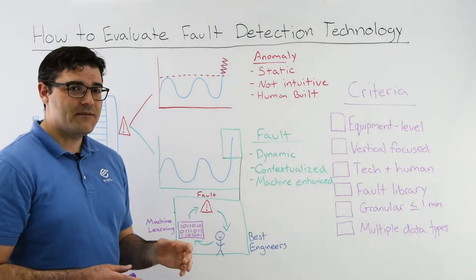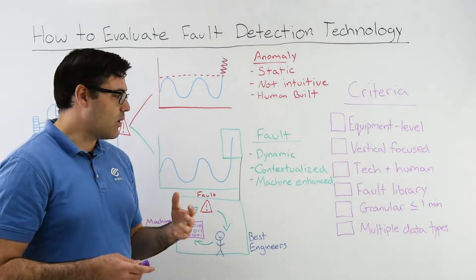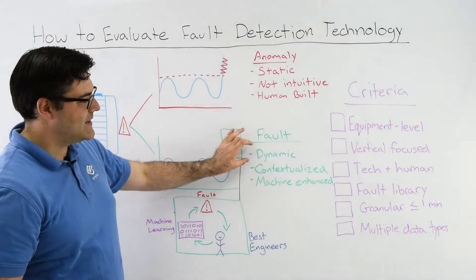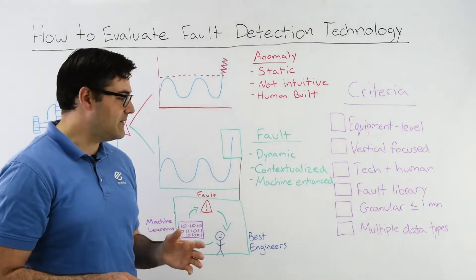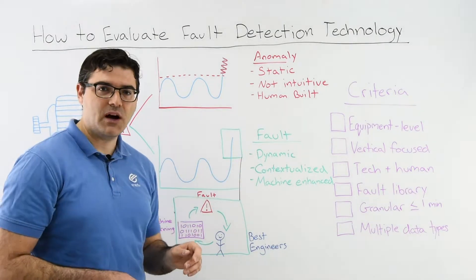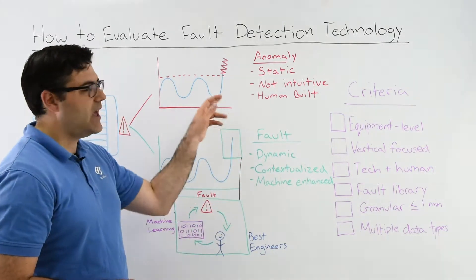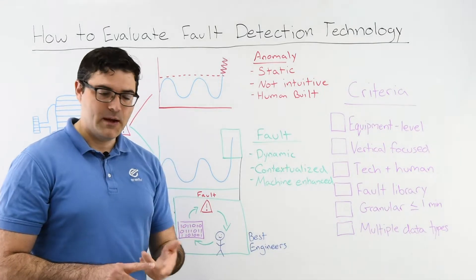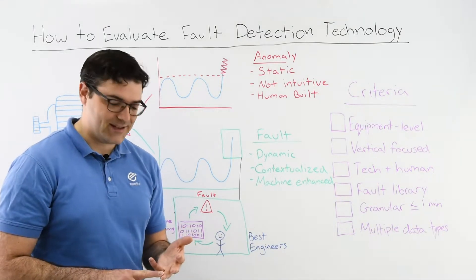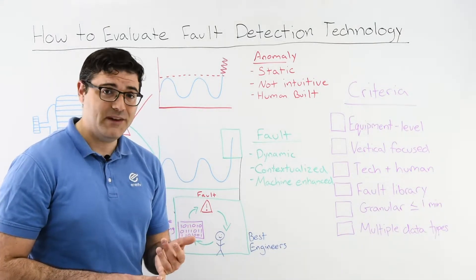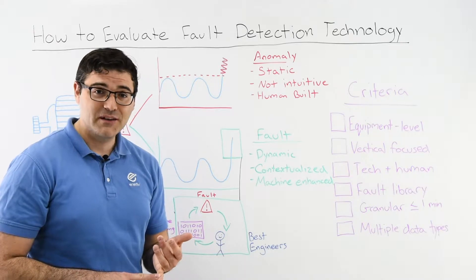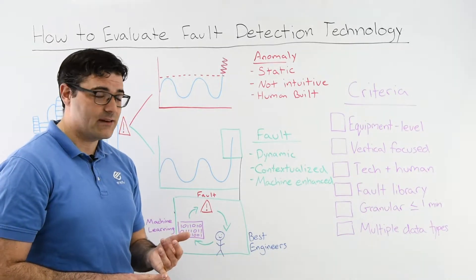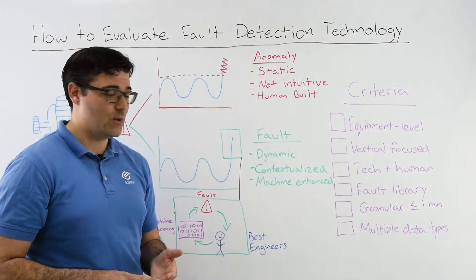Fault detection involves a lot more than just breaking a threshold. It's about having a dynamic understanding of the environment and contextualizing the problem. Not just saying that we have a spike in energy use, but my fan belt slipped, my motor failed, I have short cycling, my pump's not feeding my boilers, and I'm not going to have hot water. Those are the kinds of things you want to understand to bring the problem back to reality.